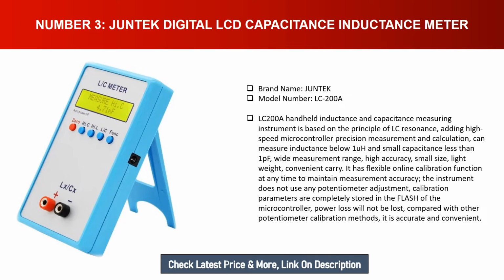The instrument does not use any potentiometer adjustment. Calibration parameters are completely stored in the flash of the microcontroller. Power loss will not cause them to be lost. Compared with other potentiometer calibration methods, it is accurate and convenient.